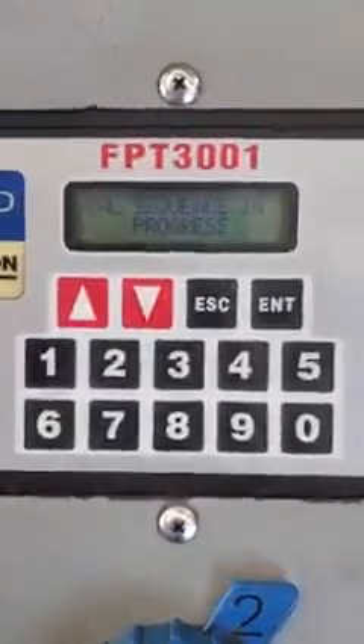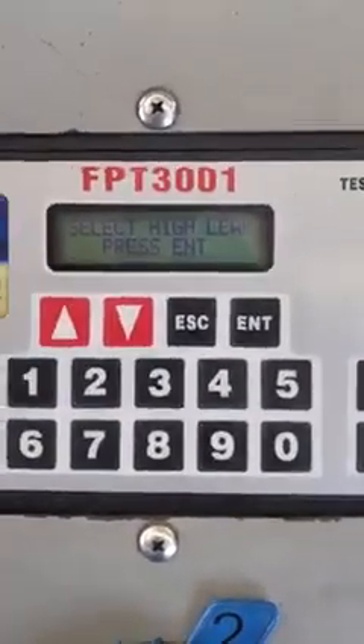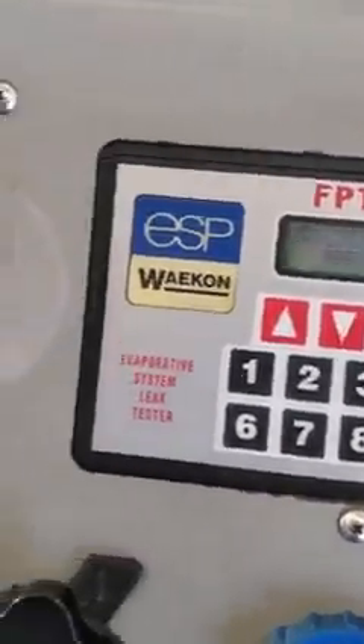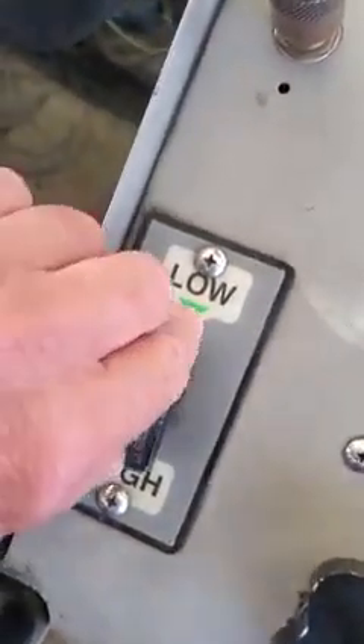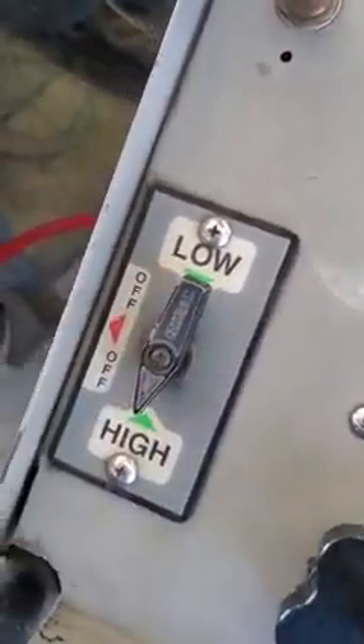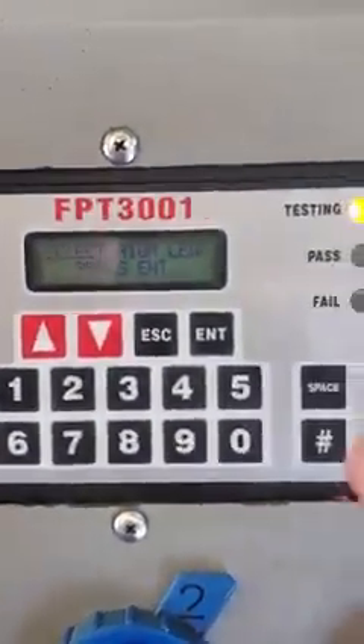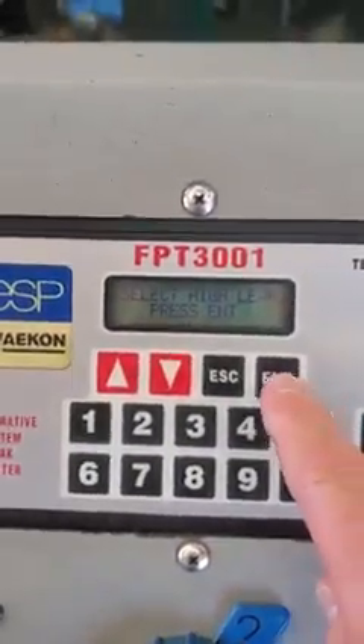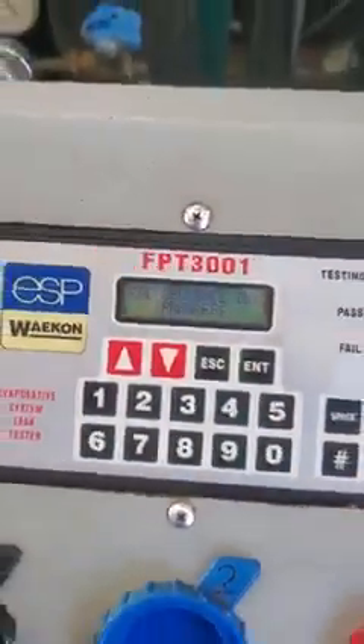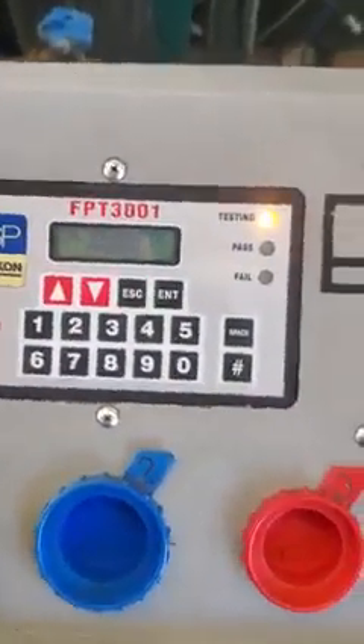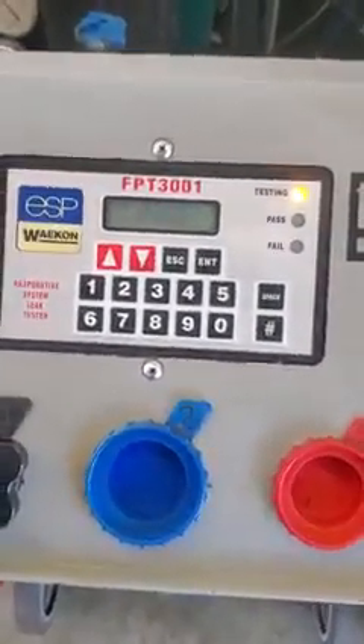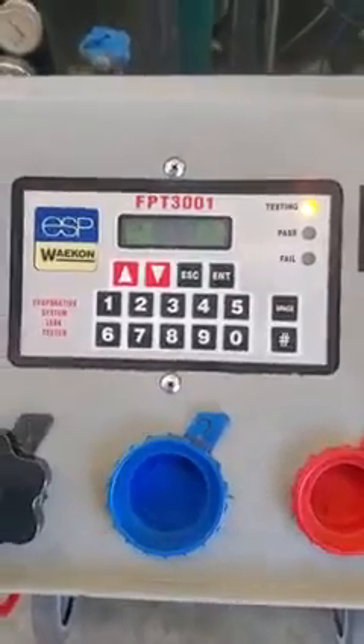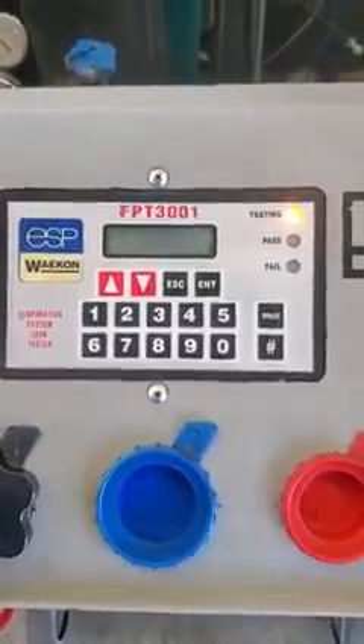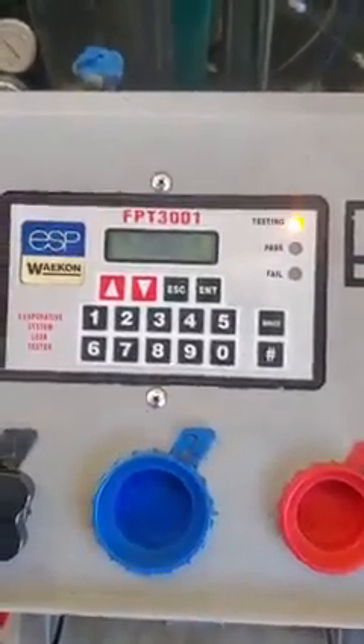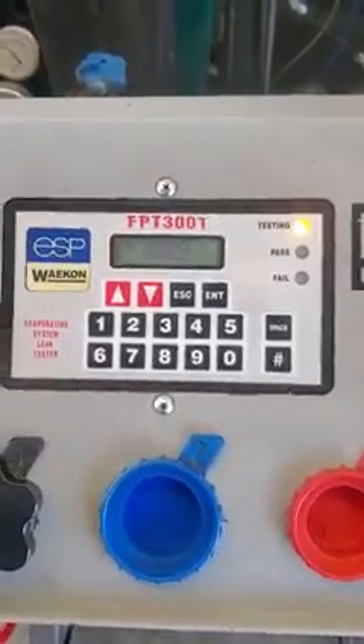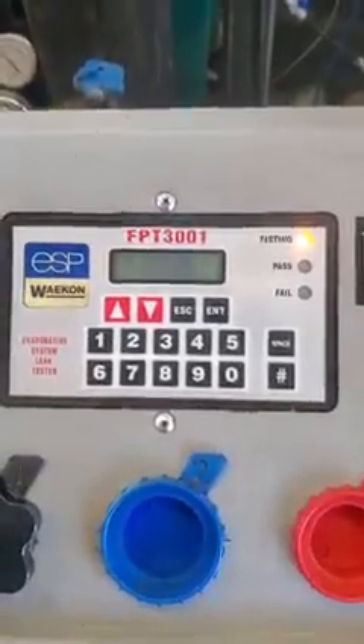So now we're still doing the low, now the machine wants to do the high. So turn your valve to high and push enter. Now your machine will do the high side of the calibration. At the end of the high, you will get a green light or a red light. Green for pass, red for fail.